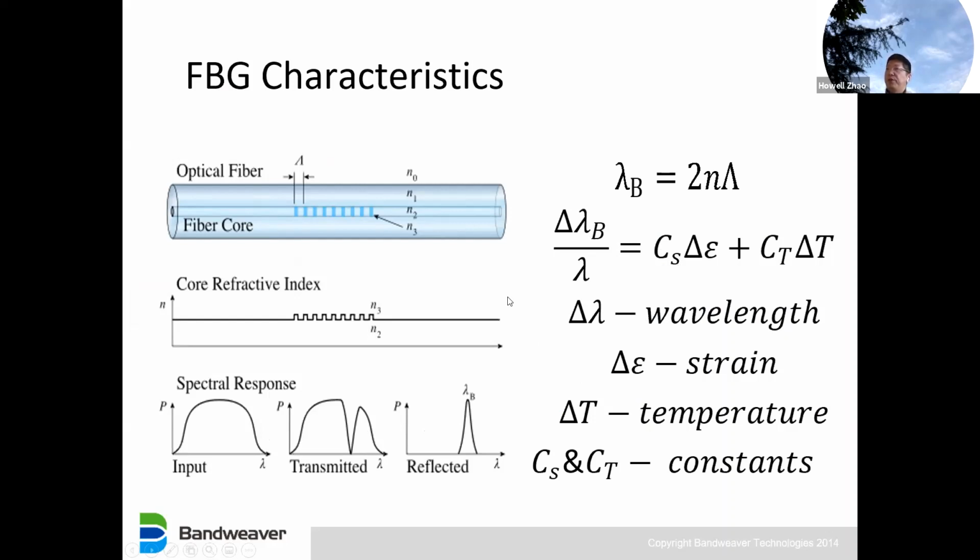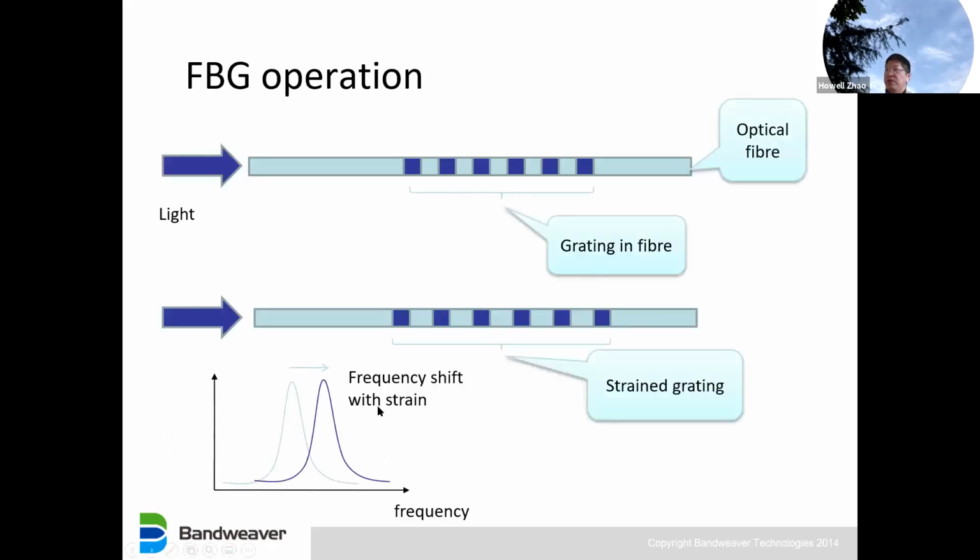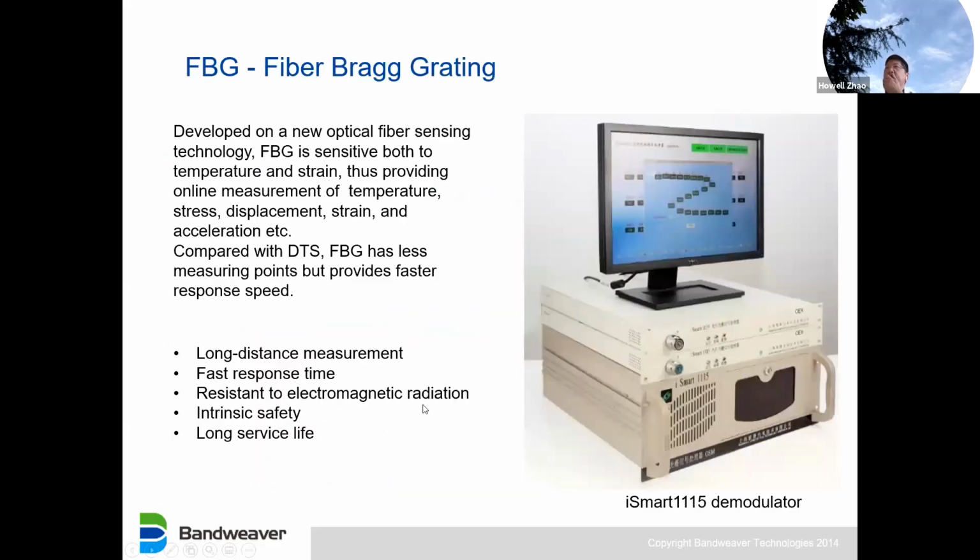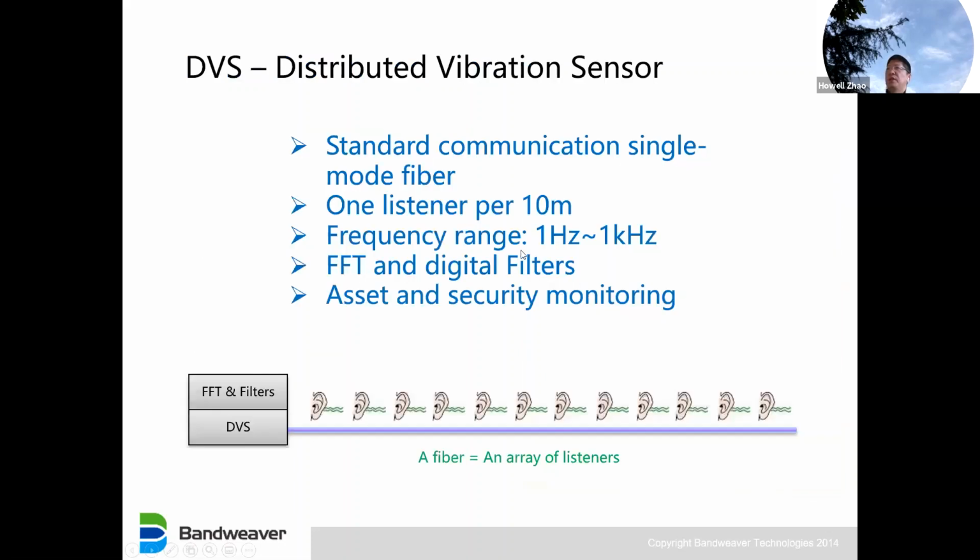So yeah, for this stage, we will not have an FBG sensor in the ID lab. But we need to know there are other fiber optic sensors called FBG sensors. This is a microstructure, and when strain or temperature changes, the central wavelength of the reflection will change. So from the wavelengths, we can get the temperature information or the strain information. Okay, so that's a box looks like from outside, with a display, and we can get multiple point temperature and strain information.